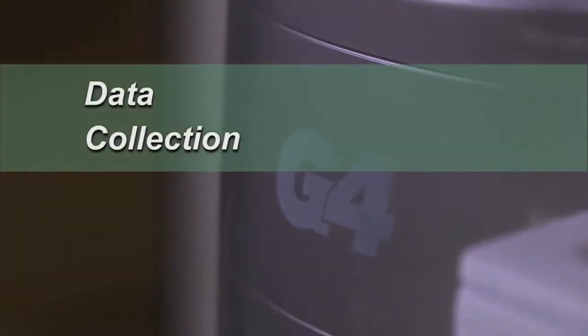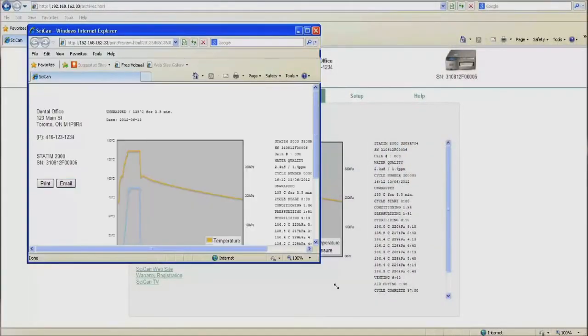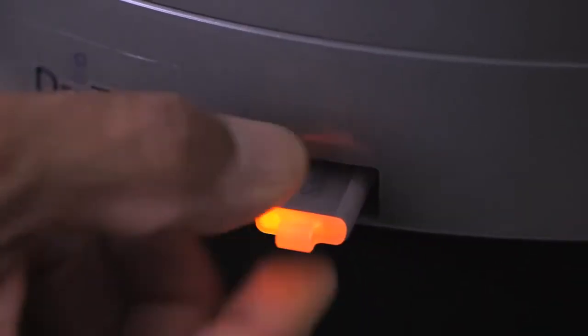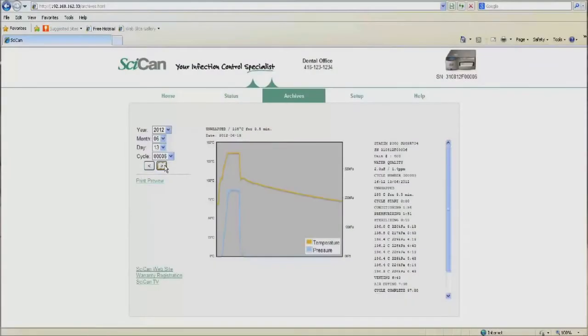Features like advanced data collection make managing information fast and efficient. Through the G4's networked portal, the Statim's current status can be viewed and all cycles and cycle graphs can be examined. Data logging is also automated. The USB flash drive engaged in the front of the unit will record all cycles and include the unit's serial number, date, cycle number, any error codes, and the confirmation of a completed cycle — including all times, temperatures, and pressure associated with the successful cycle.